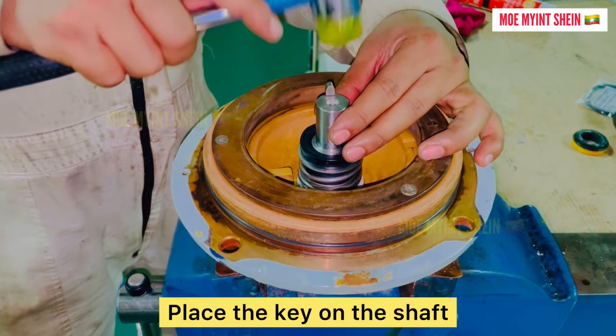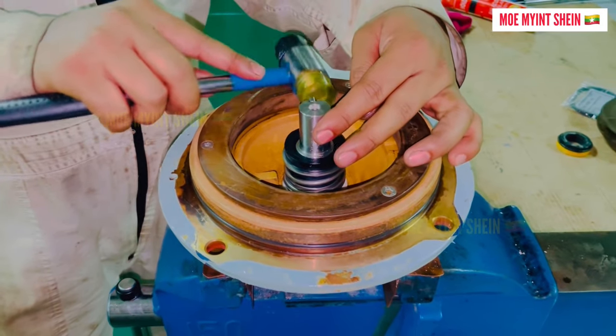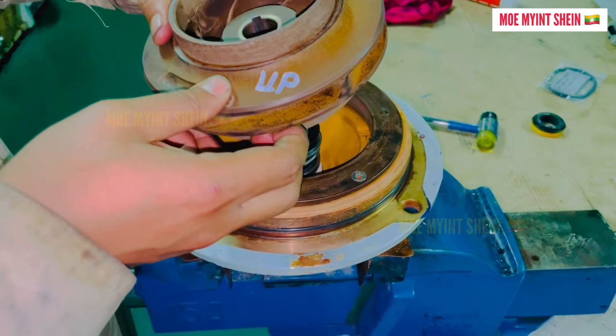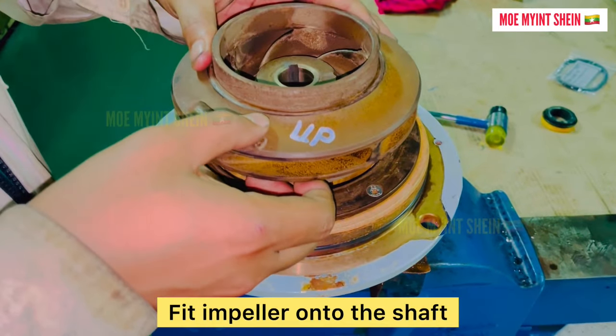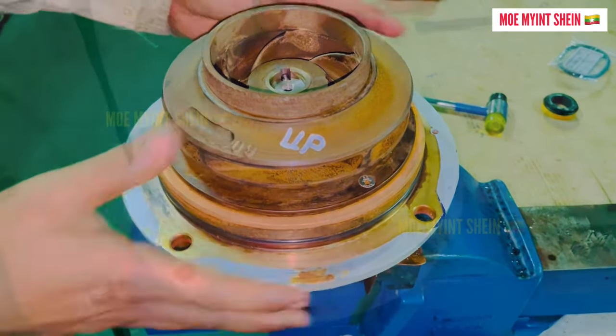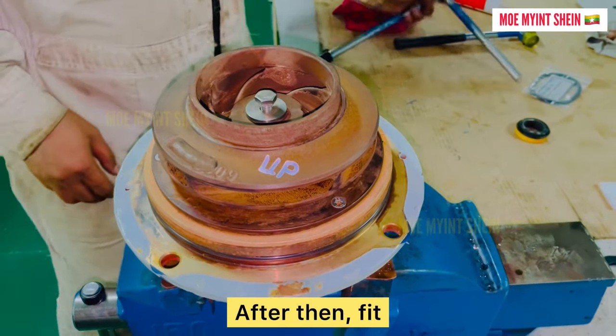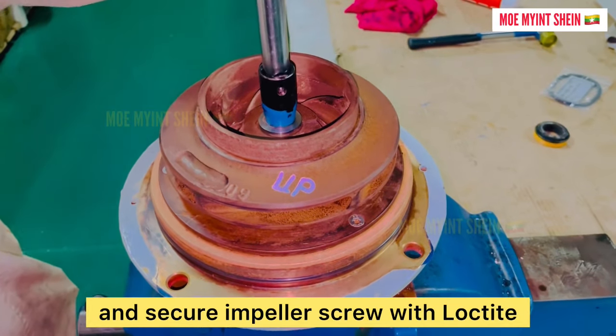Place the key on the shaft. Fit the impeller onto the shaft and confirm the impeller is in the correct direction. After then, fit and secure the impeller screw with Loctite.